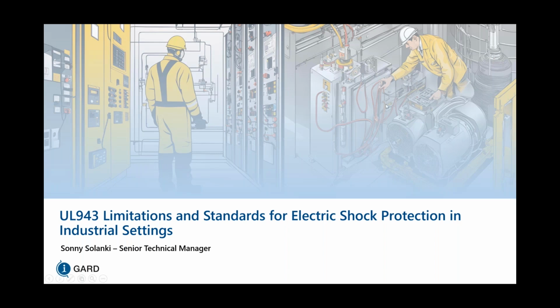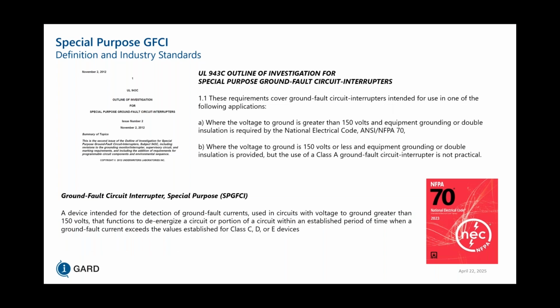So to start, usually when we're referring to special purpose GFCIs, we would look at UL943C, which is an outline of investigation, not yet a standard technically. And it outlines the purposes that can be used for ground fault circuit interrupters. So these requirements cover ground fault circuit interrupters intended for use in one of the following applications.